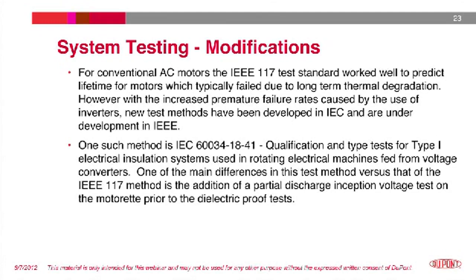However, as I mentioned earlier, there have been recent changes in insulation system testing to help address the new threats caused by the use of inverter systems in controlling low voltage motors for variable speed drives. One such test is IEC 60034-18-41, qualification and type test for Type 1 electrical insulation systems used in rotating electrical machines fed from voltage converters. In this testing, an additional evaluation of the partial discharge inception voltage, PDIV, of the motorette is included to help understand how well the system can withstand these overvoltage phenomena.